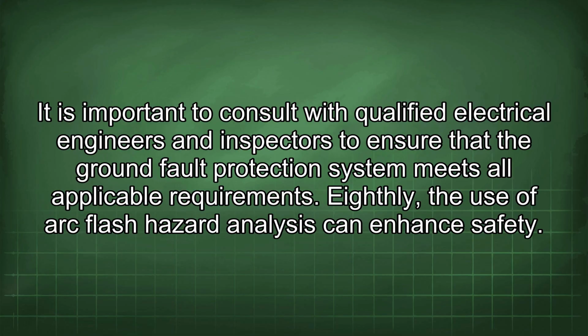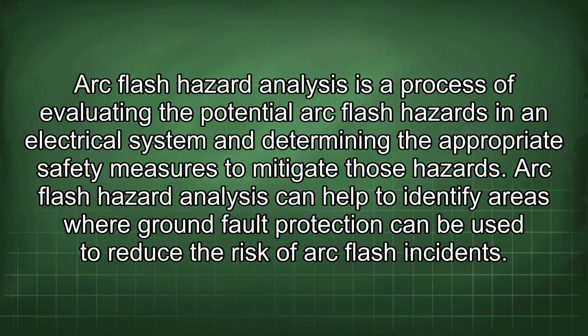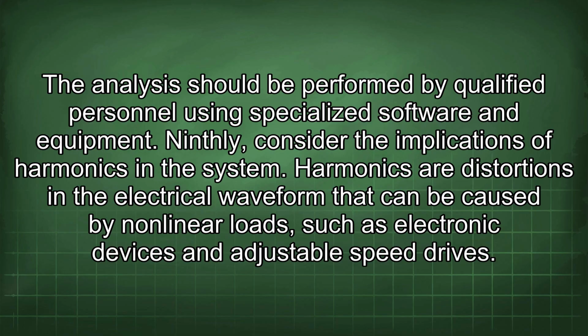Eighthly, the use of arc flash hazard analysis can enhance safety. Arc flash hazard analysis is a process of evaluating the potential arc flash hazards in an electrical system and determining the appropriate safety measures to mitigate those hazards. Arc flash hazard analysis can help to identify areas where ground fault protection can be used to reduce the risk of arc flash incidents. The analysis should be performed by qualified personnel using specialized software and equipment.